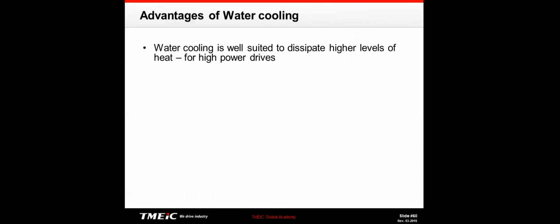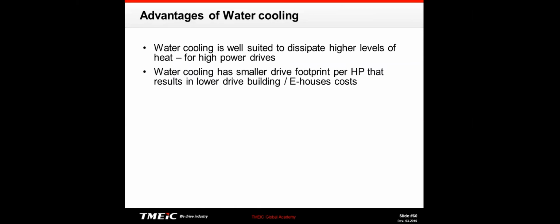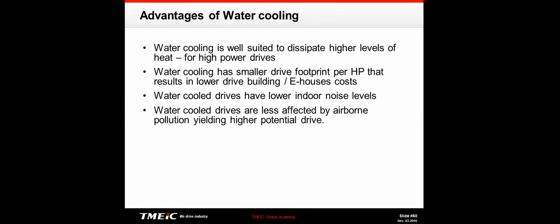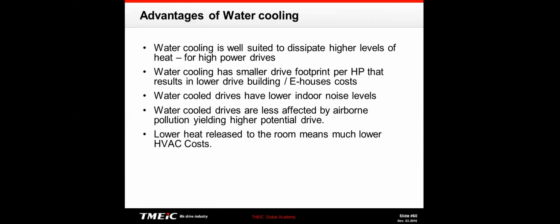Water cooling, we could spend an hour on water cooling, but with low voltage drives, in most cases, not all, but in most cases, we don't see water cooling. In medium voltage drives, when you get up into the large drives, water cooling just becomes a de facto standard. So water cooling dissipates higher levels of heat, has a smaller drive footprint, has lower noise levels, is more resistant to contamination of the air and in the facility. So water-cooled drives keep that drive very clean.